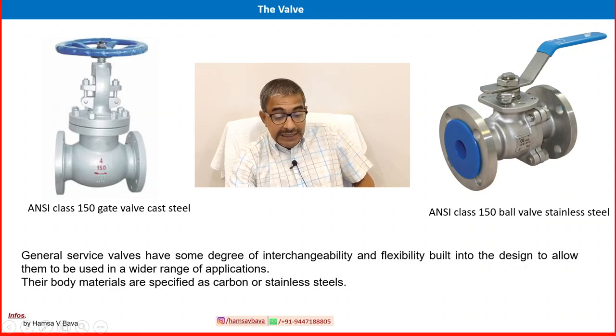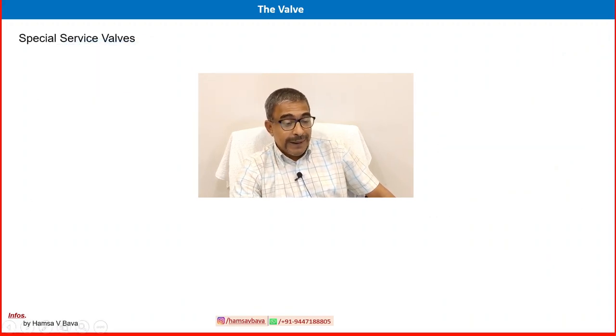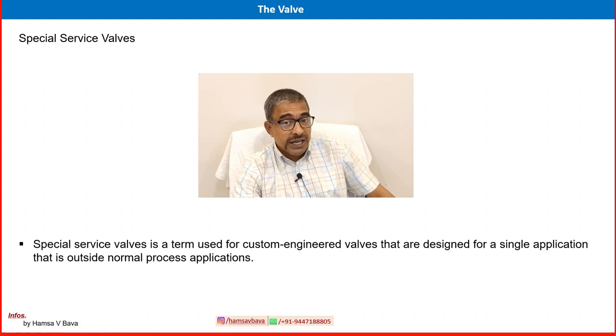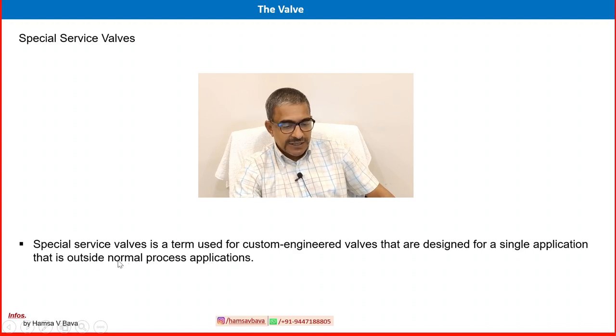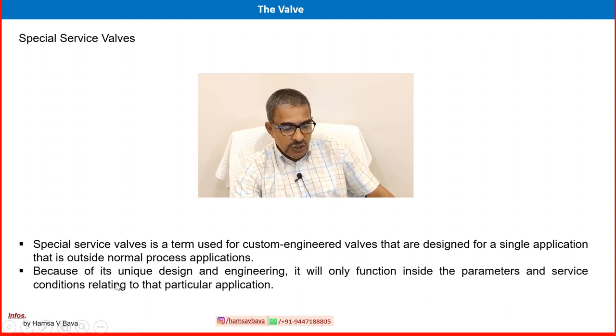One more valve type based on application classification: special service valves. Some services involve corrosive media, high pressure, flashing, or cavitation — in those cases a general service valve cannot be used, and that category is considered a special service valve. Special service valves are custom-engineered valves designed for a single application outside normal process applications. Because of their unique design and engineering, they only function within the parameters and service conditions of that particular application — not for general application.